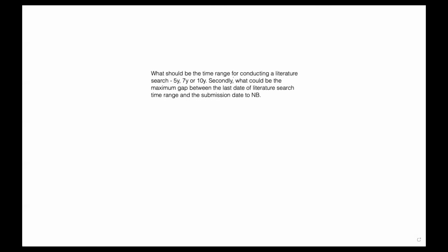Nothing less than 5. I can tell you, in our experience, it's never been less than 5 for an initial CER or an initial search, not annual updates. Because in an annual update CER, if you keep all of your same systematic literature review criteria and search terms, then all you're doing is a gap search from last year's closing date to this year. So that's been our experience.